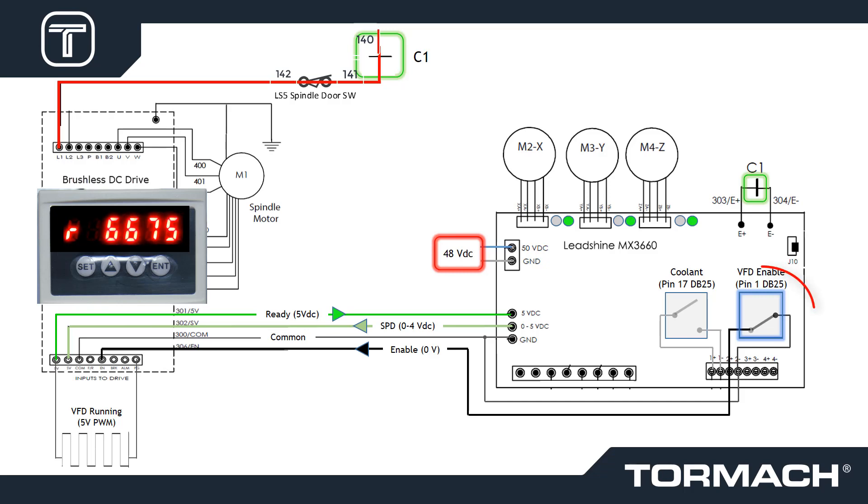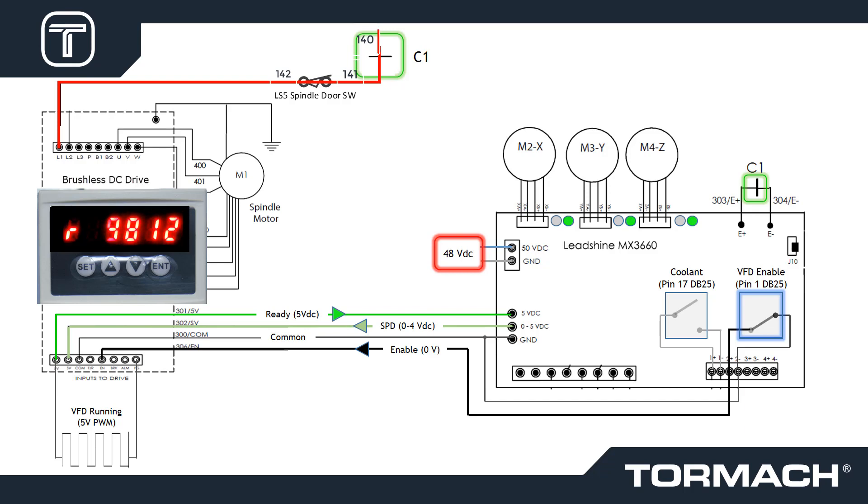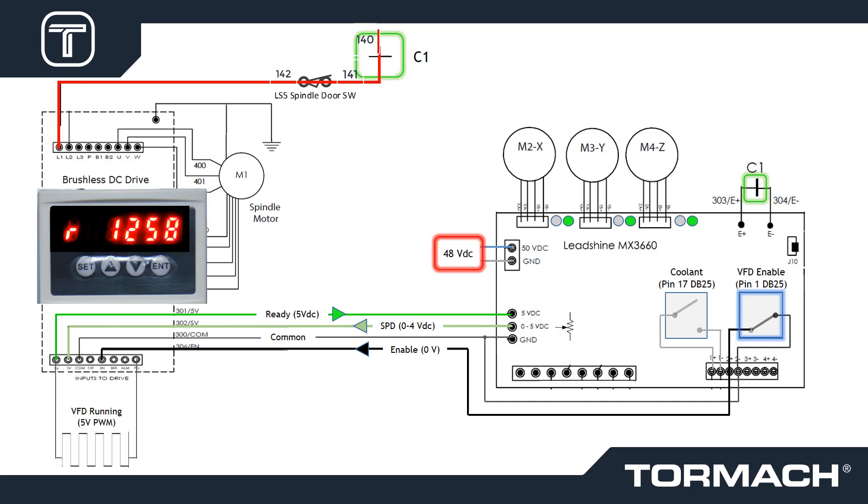Schematically, I illustrate this as a contact closure. Wire 302 provides a voltage between 0 and 4 volts representing the spindle speed between 300 and 10,000 RPM.